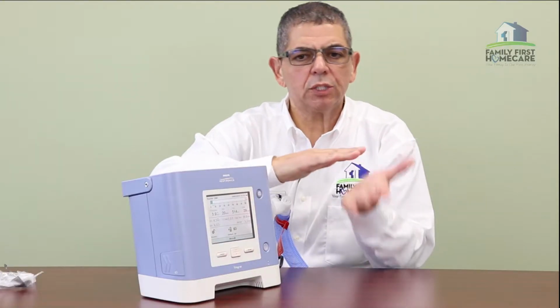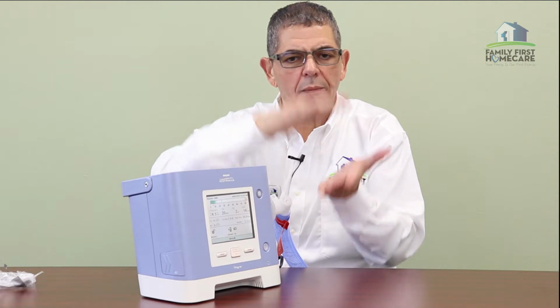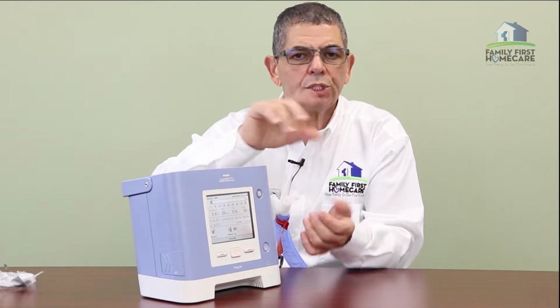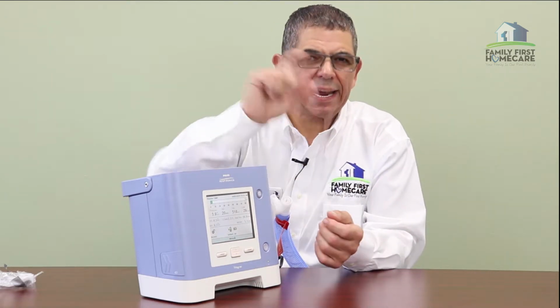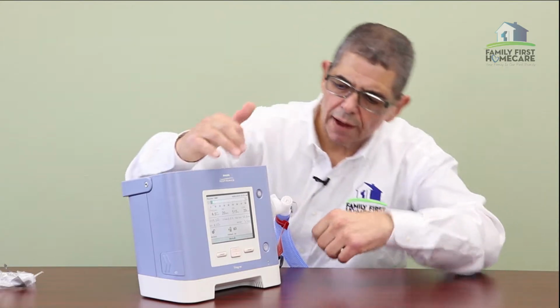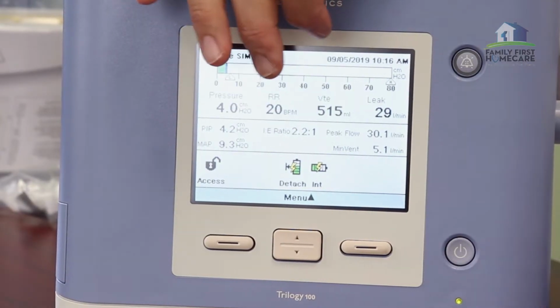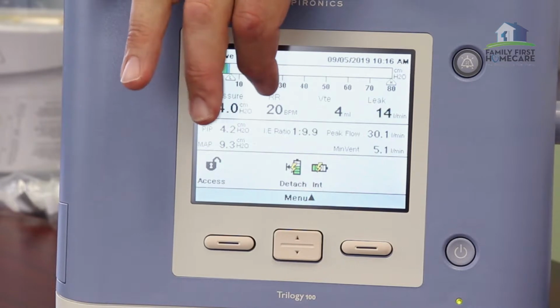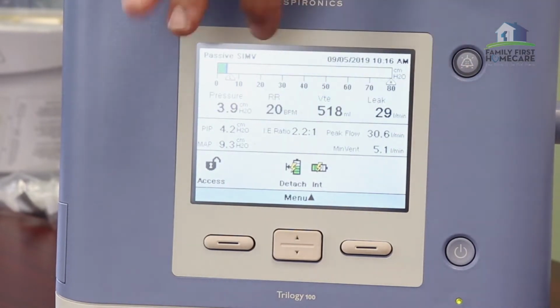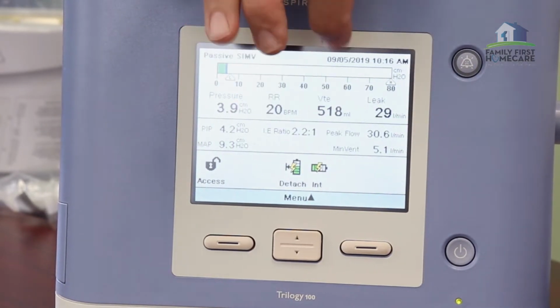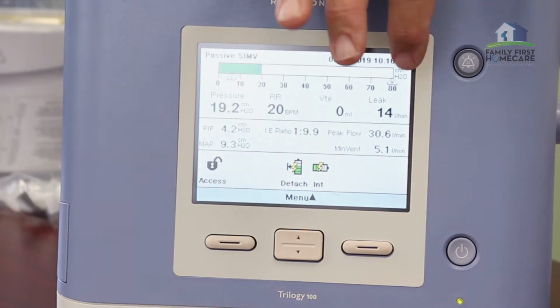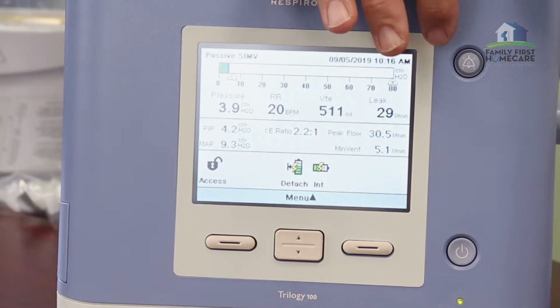If it's ranging between 34 and 37, going up and down a little bit in that area, look at it for 5 seconds and get the average, because that will be fine for the respiratory rate. I'll explain why, because that will be reflected down here in the minute ventilation. Right here is the VTE, that's the tidal volume. You'll notice a new reading called leak.